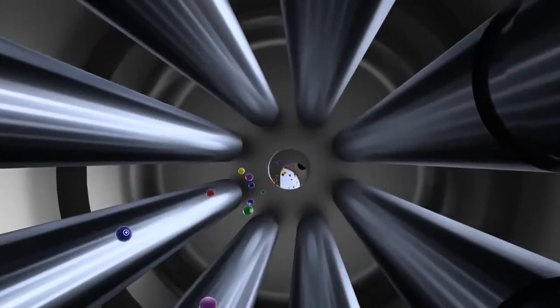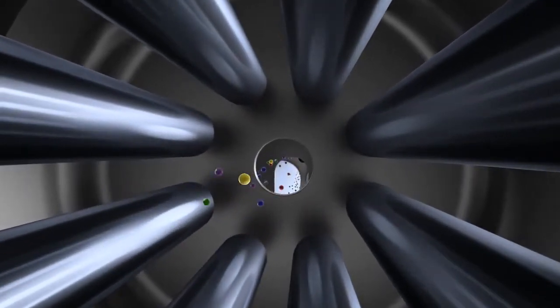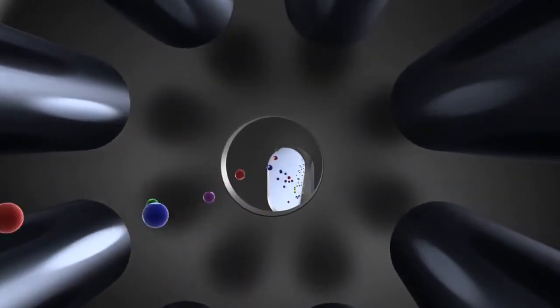KED is a simple and reliable process based on the fact that polyatomic ions are larger, collide more frequently with the cell gas, and therefore lose more energy as they pass through the cell. The difference in ion energy at the cell exit means that analytes and polyatomics can be separated with a fixed bias voltage. The ORS-3 uses a narrow internal diameter octopole ion guide, which maintains ion focus and provides high transmission even at the high cell gas pressures needed for effective KED.